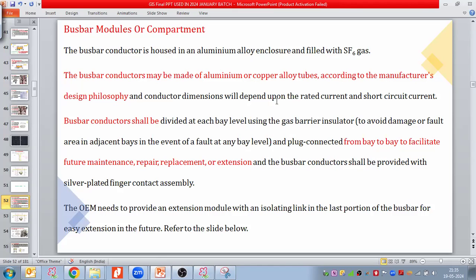This is point number one. Point number two, the bus bar conductor shall be divided at each bay level, that we just discussed, using the gas barrier insulator. The barrier insulator, why? Just to avoid damage or fault area in an adjacent bay in the event of a fault at any bay level. So due to that reason, we are using the insulator.